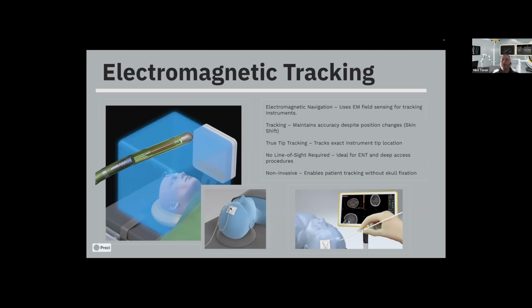and it's a non-invasive tracking technology from the patient's point of view, in that the patient's reference can just be stuck onto the skin, and as long as the skin doesn't move, we can now rotate the patient's head and move the patient's head around, or be completely non-invasive to either do something like a pediatric shunt or an ENT procedure, etc. But this doesn't require line of sight as long as the electromagnetic field doesn't get distorted. So it is susceptible to heavy metals. Any of the sort of beds that have got major round ring closed loop type handles, etc., made out of stainless steel can affect us. So generally we're looking for carbon fiber tables and things. So obviously heavy metal in that space does affect it, but it's definitely got its place where line of sight and pinning isn't an option.